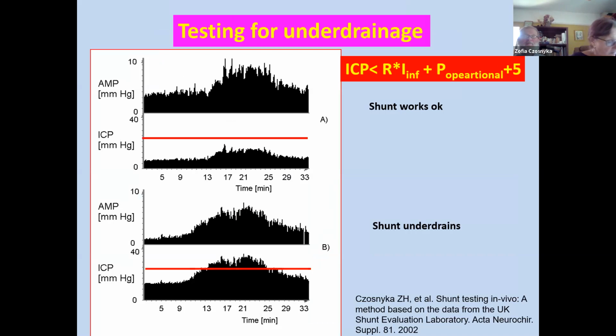Testing for underdrainage. We found that for assessment of underdrainage, a key parameter is the critical pressure. This is the pressure value that should not be exceeded during infusion with a properly functioning valve. Again, the critical pressure can be calculated on the basis of the laboratory results as the hydrodynamic resistance of the valve, value from the laboratory, times the applied infusion rate, plus the operational pressure of the valve from the laboratory, plus 5 millimeters of mercury. And here the critical pressure has been marked with a red line.